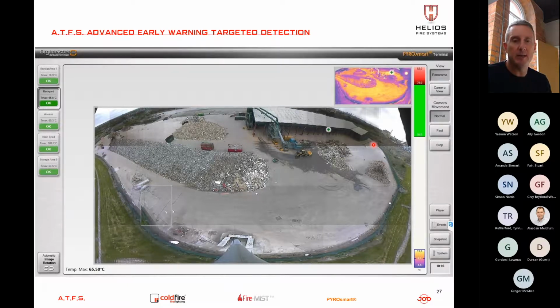The only downside to larger areas is that a fire or hotspot has to be bigger at the extremities, away from where the fire is. So if we had a hotspot here, a 50mm size is 50 millimeters, but that same 50 millimeters over here may have to be half a meter before we'll actually detect it, because of the distance away. Not a great deal we can do about that apart from putting more cameras in.